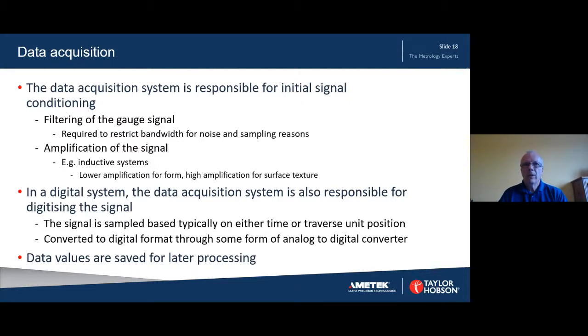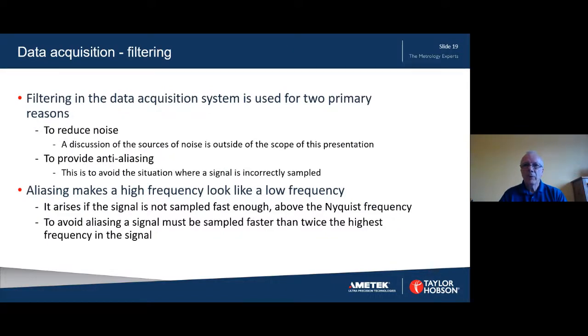In a modern digital instrument, the data acquisition system is responsible for converting the signal from analog to digital. This implies some form of sampling which is usually triggered either by timer or some feedback from the traverse unit position. There might also be a need for amplification, especially where there are selectable ranges such as in inductive systems. However, there will almost certainly be a filtering stage. Filtering is important for two primary reasons: to reduce or suppress noise, and to ensure that sampling conditions are met by limiting the upper frequencies admitted to the analog to digital conversion stage. If the upper frequencies are not adequately suppressed, then aliasing may occur. This is where a signal is sampled more slowly than necessary, resulting in the sampled signal appearing like a lower frequency signal.